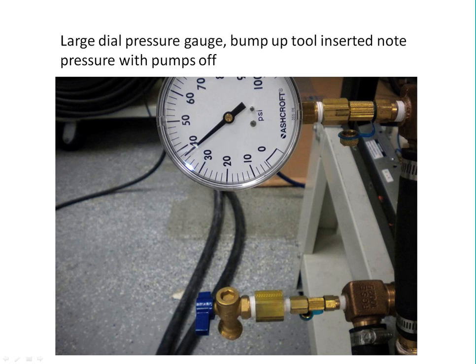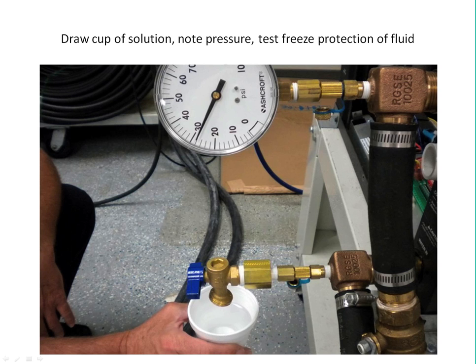It really doesn't matter which one goes where, whichever one works out best for what you're trying to do here. So you insert that large dial pressure gauge and that bump up tool each into a PT port, again with the pumps off, so power that unit off, and I want you to record that static pressure. You see this one is almost 38 psi. Next, I want you to take a relatively modest sized cup, not one of these truck stop big boy commuter mugs.